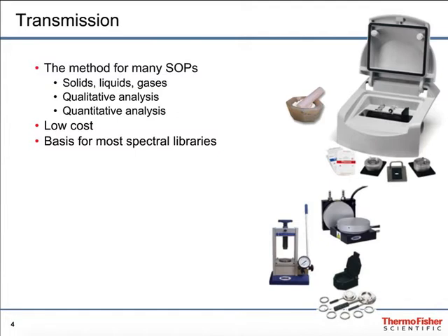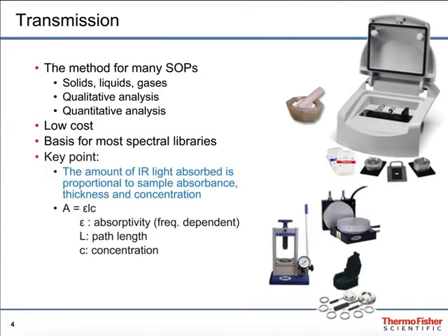The key point for transmission is that the amount of IR light absorbed is proportional to three things: the absorptivity, symbolized as epsilon; the path length, L; and the concentration, C, of the number of molecules in the beam. The epsilon gives the spectrum its shape, the absorptivity being a function of each wavelength or wavenumber in the spectrum, and C, the concentration, is where the quantitative information comes from.